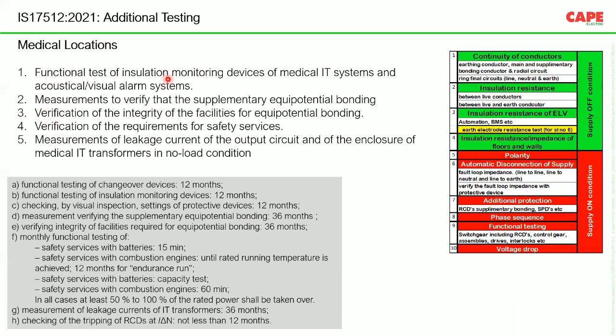The first one is that the insulation monitoring device should be tested. The second and third are both related to shock reduction: supplementary equipotential bonding, and facilities for equipotential bonding, the efficiency of these bondings. Please note that bonding means you take a wire and connect it to metal parts. Then you check and find out the actual potential difference between these two parts, and it should be lesser than 40 millivolt, for example.